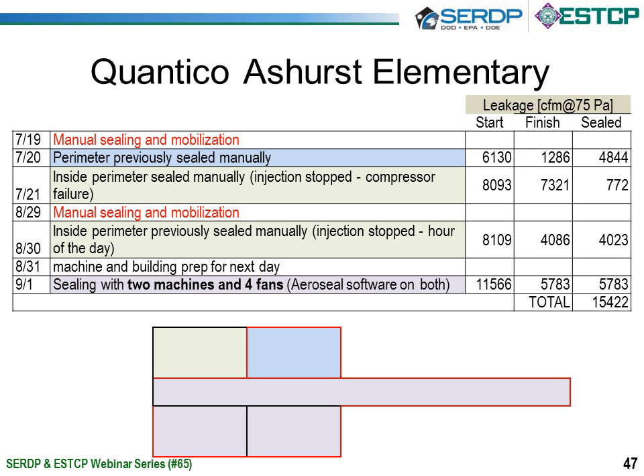So you see we came back the next month and sealed the rest of the building from 8,100 down to 4,000, sealing about half the leakage. And then we decided to try to seal the remaining part of the building in one try. So we got an extra machine for the sealing, and we were able to seal two classrooms and the hallway all at one time. When you do that, obviously you're not compartmentalizing between the spaces, so we didn't need to do any manual sealing between the classrooms, and we were able to reduce the leakage from 11,500 CFM at 75 down to 5,800 or so.